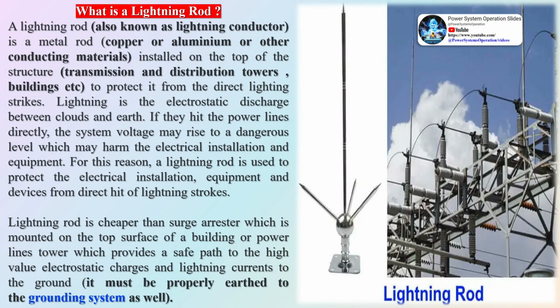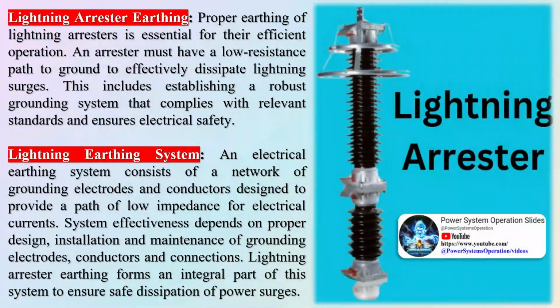Surge arrestors are connected between phase and ground terminals. If we cut open any lightning arrestor, we can see the line terminal, which is connected to the phase live terminal, and the bottom terminal, which is connected to the ground. The main component of lightning arrestors is a column of ZnO pieces, which plays an important role in LA working. The characteristics of zinc oxide are non-linear: ZnO offers relatively high resistance at a low voltage level and very low resistance at a high voltage level.